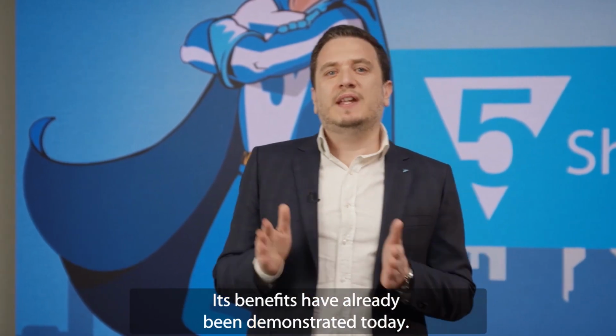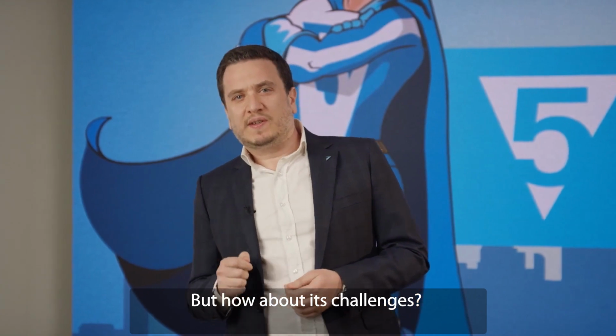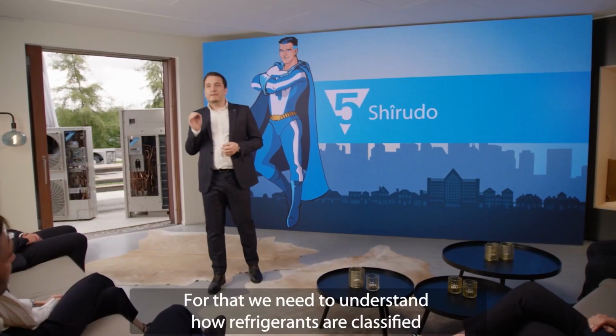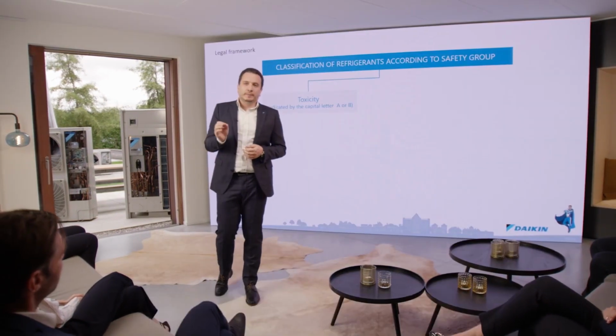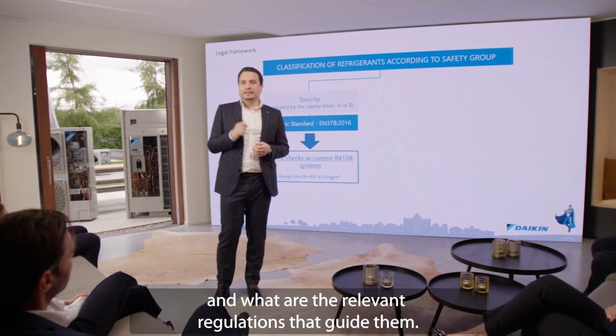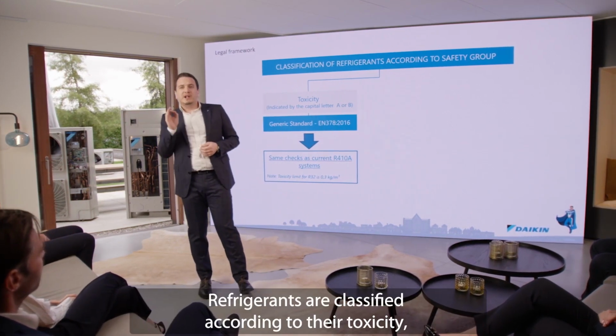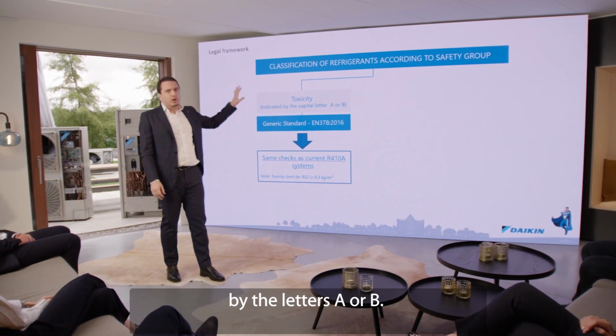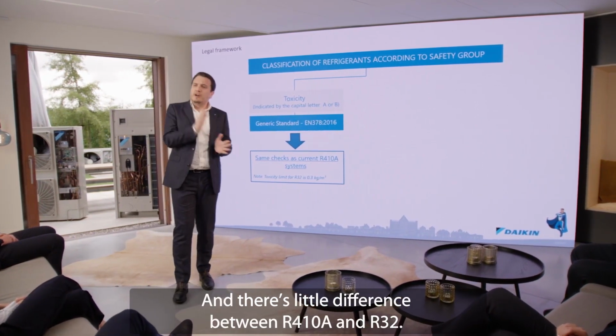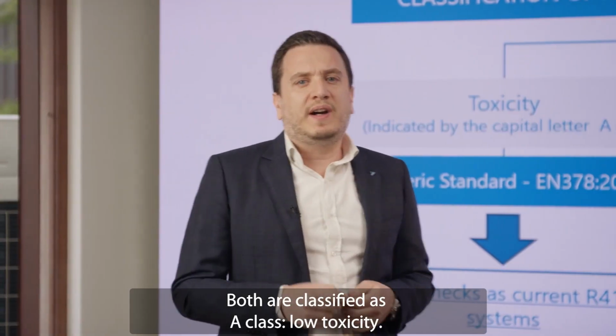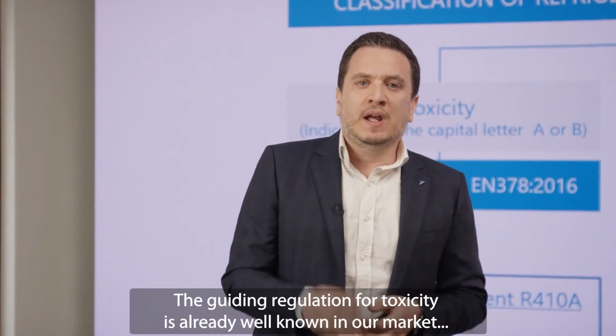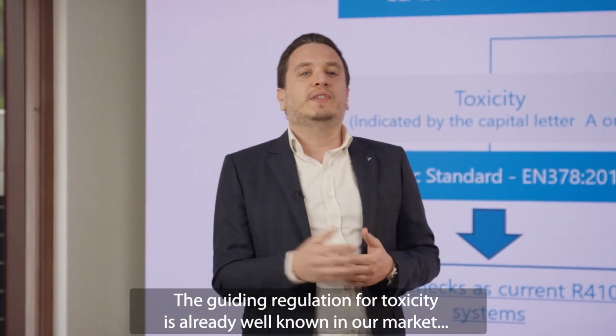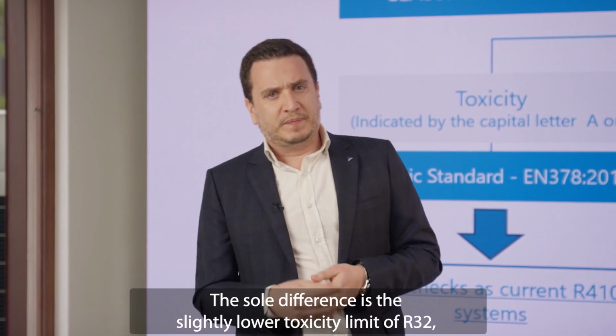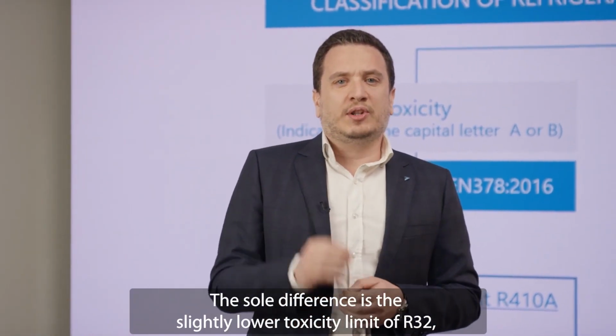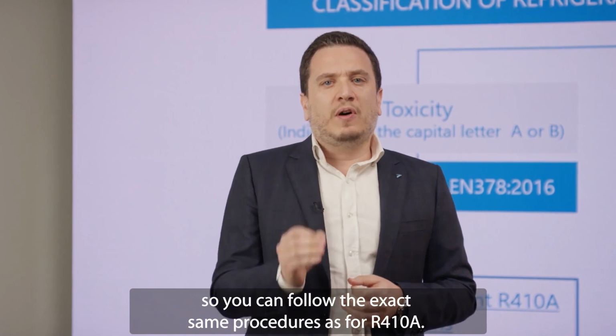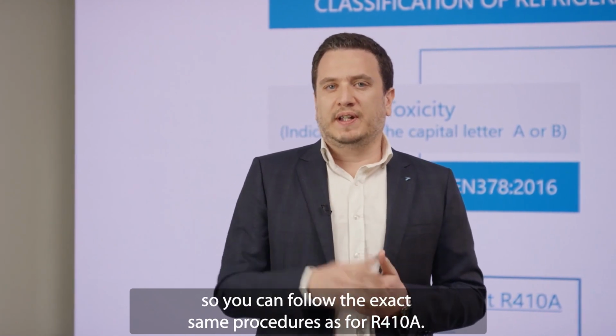Its benefits have already been demonstrated today, but how about its challenges? For that, we need to understand how refrigerants are classified according to their safety group, and what the relevant regulations that guide them are. Refrigerants are classified according to their toxicity, by letters A or B, and there are few differences between R410A and R32. Both are classified as class A, low toxicity. The guiding regulation for toxicity is a well-known standard in our market, EN 378, and the sole difference is the slightly lower toxicity limit of R32, so you can follow the exact same procedures as for R410A.